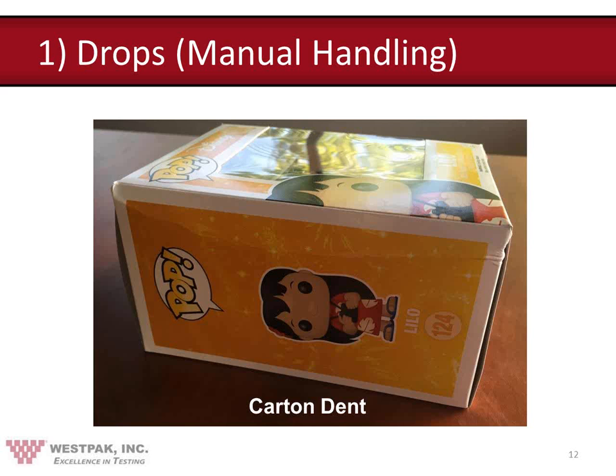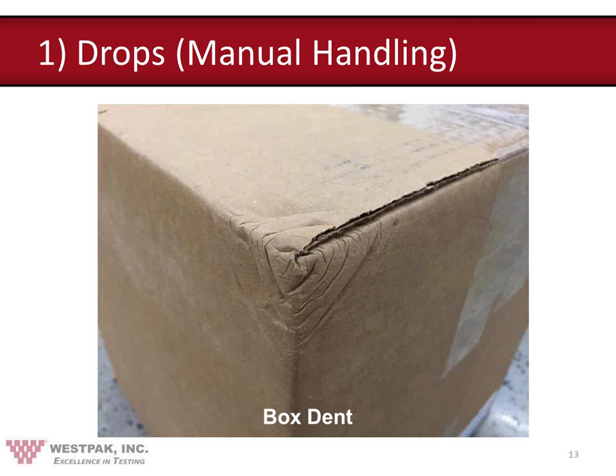Corner denting is a common damage type. Depending on your acceptance criteria, the primary concern for a medical device industry customer is to ensure the primary package remains sterile. Even though corner denting may not cause conceivable damage to the product, you have to be concerned about the condition of the package as well. People make judgments about that, and there's no standard for it — but be aware. Would you want your child operated on using a product shipped in a visibly damaged package?